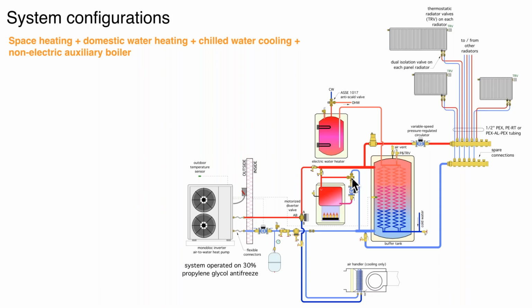One option is Caleffi does make a valve called Thermal Protect, and it's simply a thermostatic high flow capacity three-way valve. And what this will do is, as this boiler is warming up, it will simply recirculate the fluid. So it allows that boiler to come up to temperature quickly because, in effect, it's disconnected it from any load other than just maybe 2 or 3 gallons of fluid here in this piping. And once this sensing element senses that the return temperature is high enough, it'll start opening the cold port and closing this bypass port. And now we're allowing some of that flow to go out.